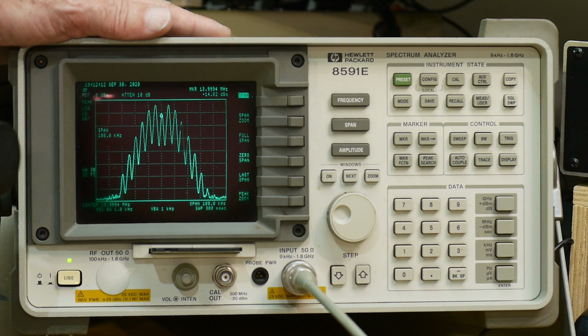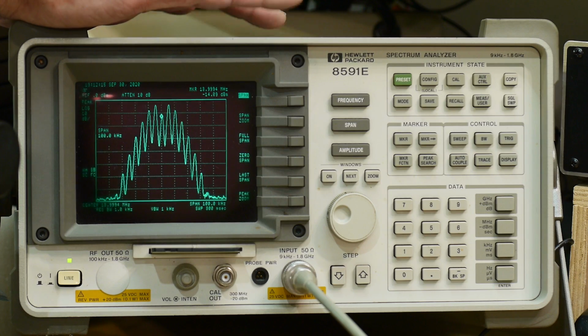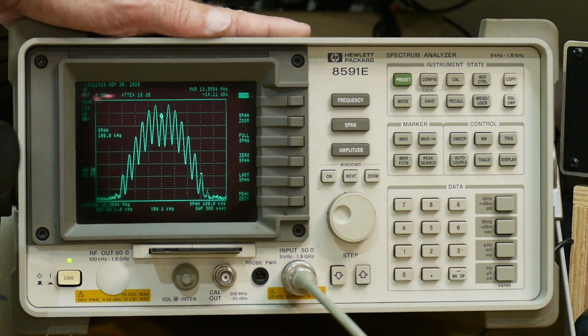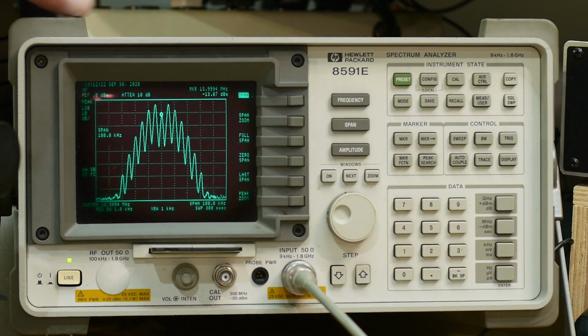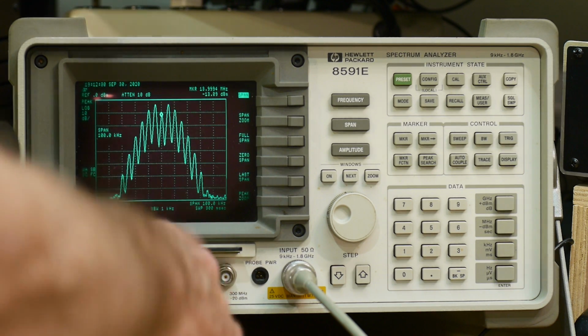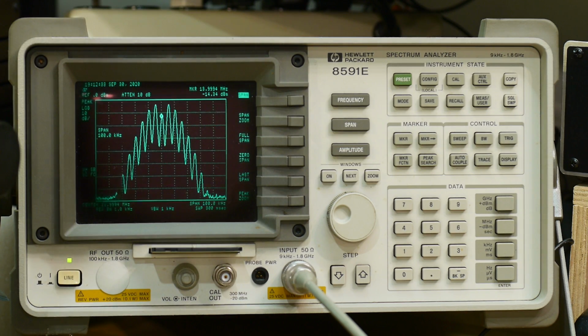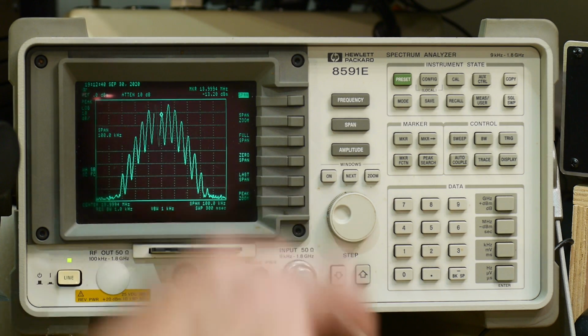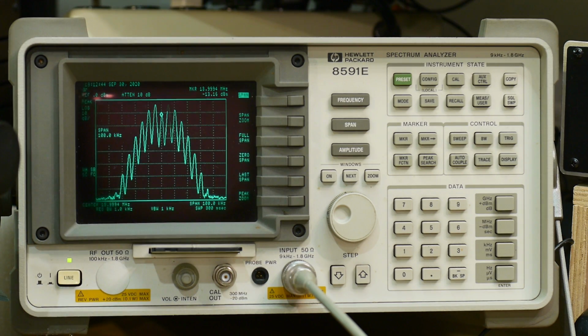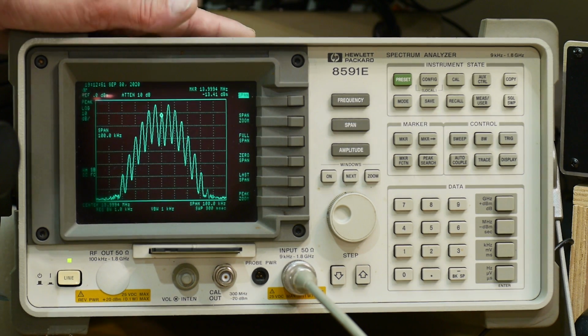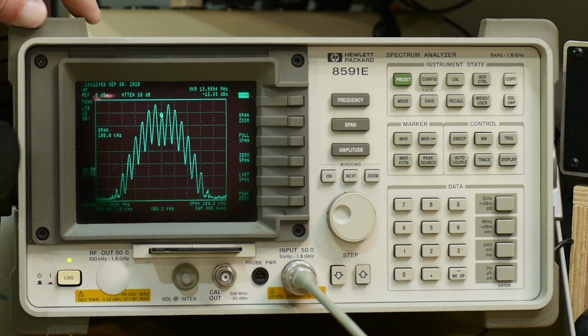One of the options is an oven-controlled oscillator. So this thing is super accurate, 0.007% or something like that, something crazy. It's got an oven in it, so it should be really, really stable. But the really good one was the very low bandwidth option. This will go down to 30 hertz. It has an option where it's 30 hertz, 100 hertz, 300 hertz. That was the option that you bought, and this one comes with it. So I can measure a 30 hertz deviation between things. It's specified down to 1 kilohertz; it'll go from 1 kilohertz to 1.8 gigahertz. Pretty cool.